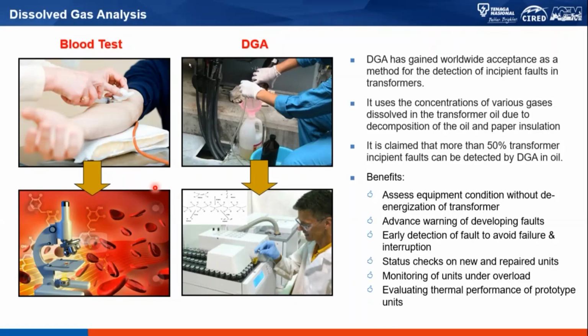So are we doing the right thing? We can use DGA to know the performance of the repair that has been conducted. And of course, we can evaluate the thermal performance of the units, in terms of the prototype units, because right now, if the transformer is to be conducted with temperature rise test, we can incorporate DGA into the test to know whether or not the design is what has been expected through the specification that has been specified for the transformer.